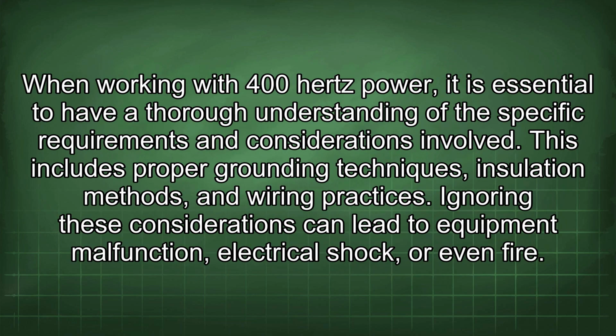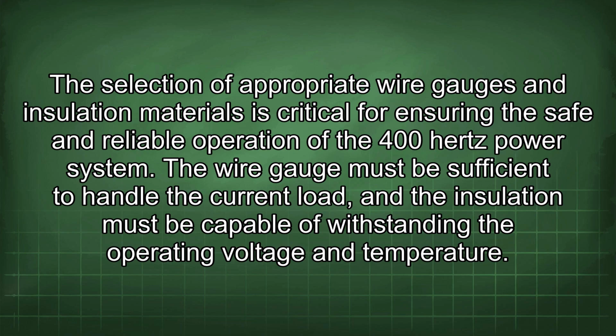When working with 400 Hz power, it is essential to have a thorough understanding of the specific requirements and considerations involved. This includes proper grounding techniques, insulation methods, and wiring practices. Ignoring these considerations can lead to equipment malfunction, electrical shock, or even fire. The selection of appropriate wire gauges and insulation materials is critical for ensuring the safe and reliable operation of the 400 Hz power system. The wire gauge must be sufficient to handle the current load, and the insulation must be capable of withstanding the operating voltage and temperature.